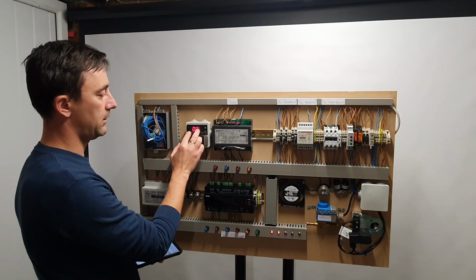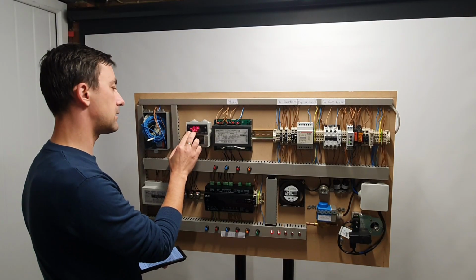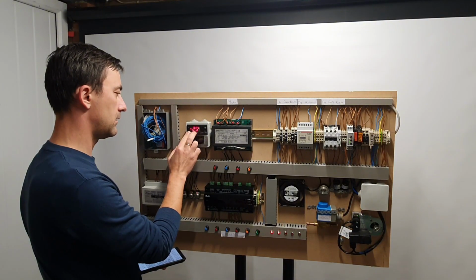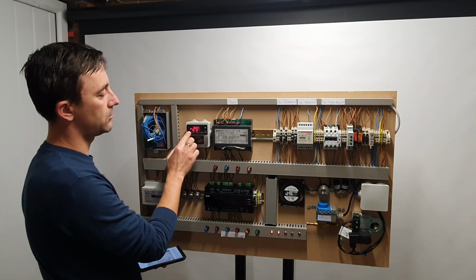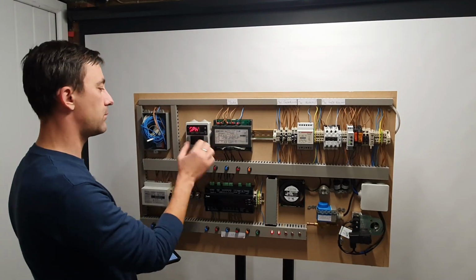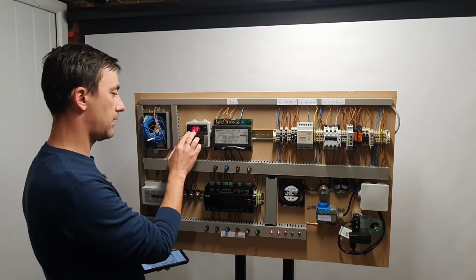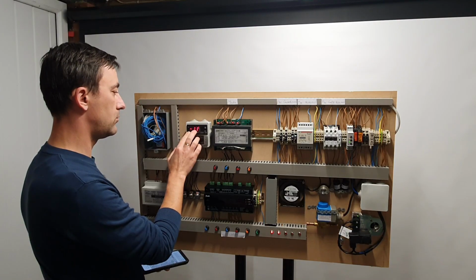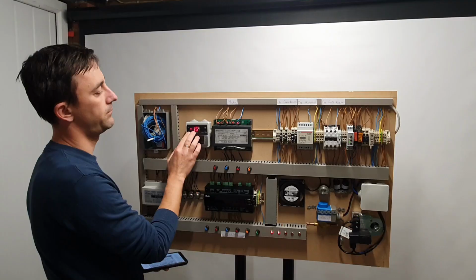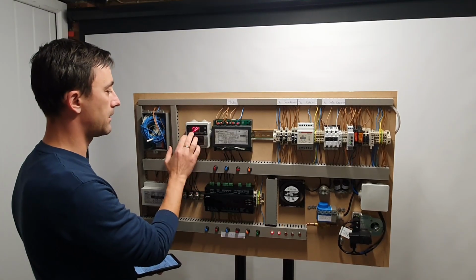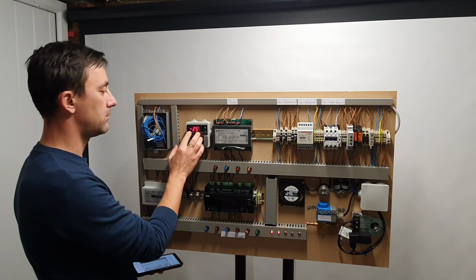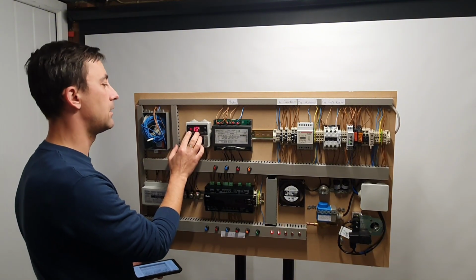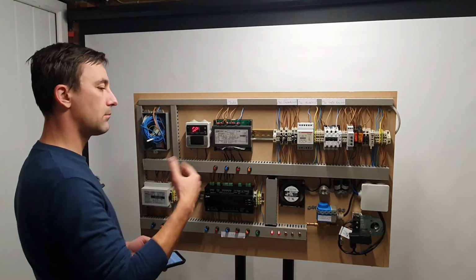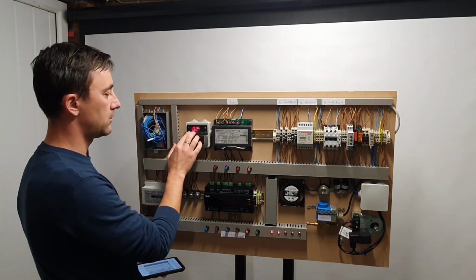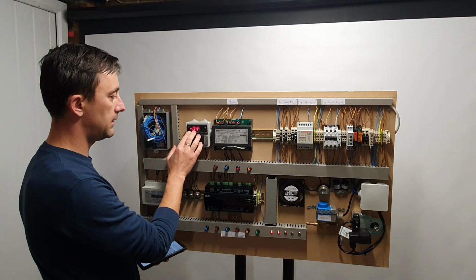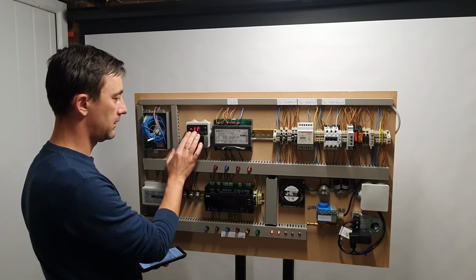Set point low is set to 0. So if I want to commission it as a freezer, I have to lower this. So we'll lower it to -25. That's the range of the set point. Set point high, I'll set this to -15. Okay, so that means set point low -25, set point high -15. That means I can set this between -24 and -15. So we shall put a set point of -18, which is SP.